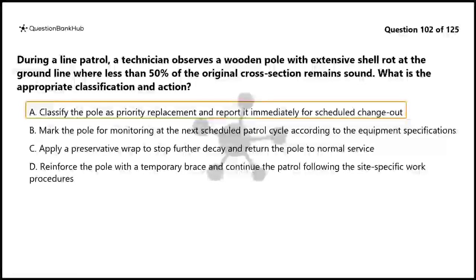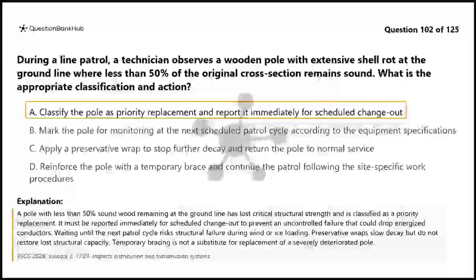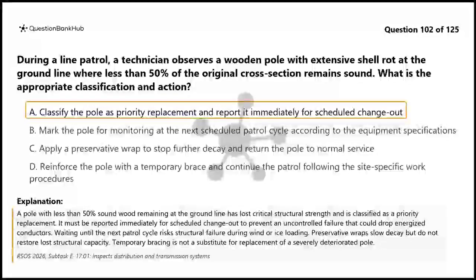The correct answer is A. A pole with less than 50% sound wood remaining at the ground line has lost critical structural strength and is classified as a priority replacement. It must be reported immediately for scheduled changeout to prevent an uncontrolled failure that could drop energized conductors.